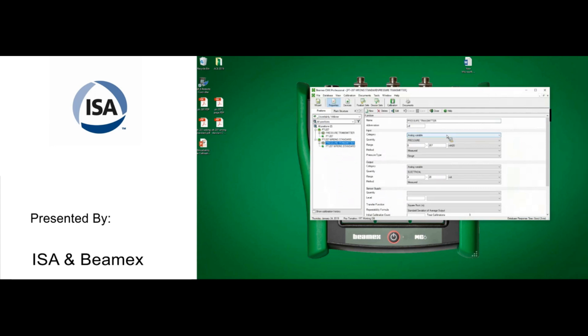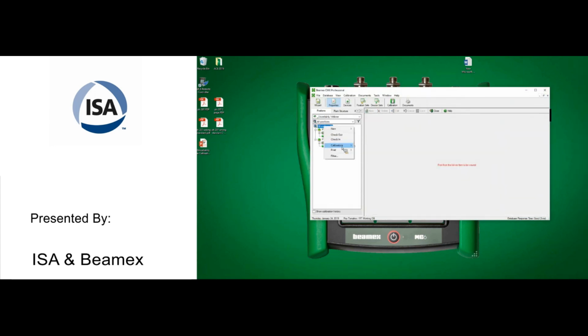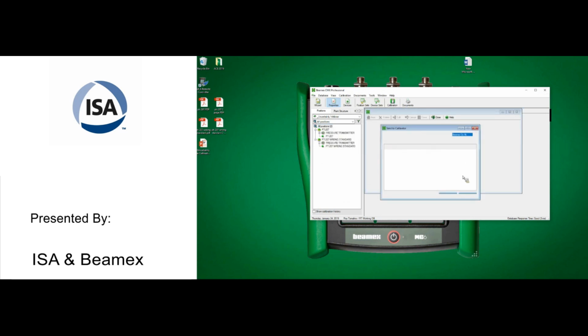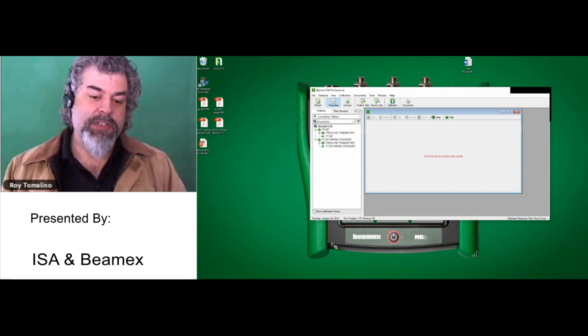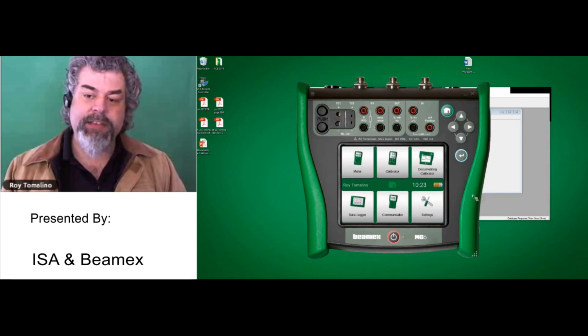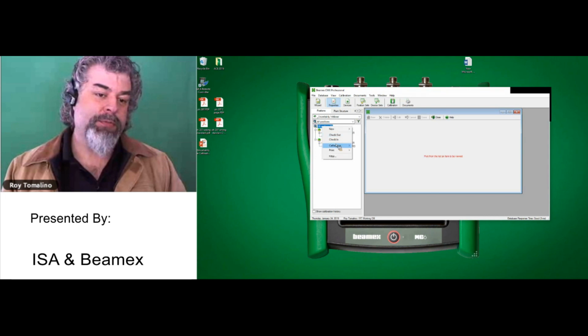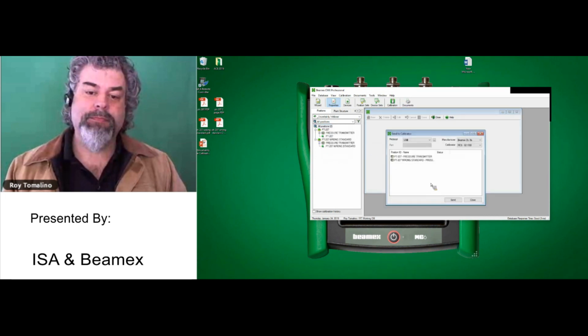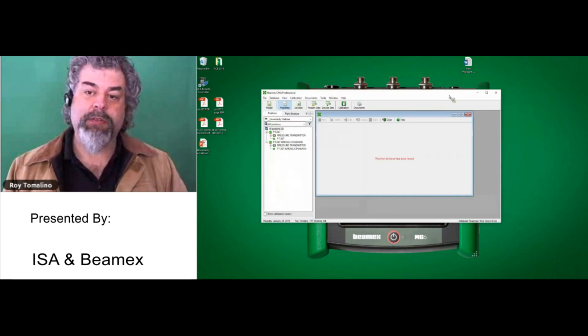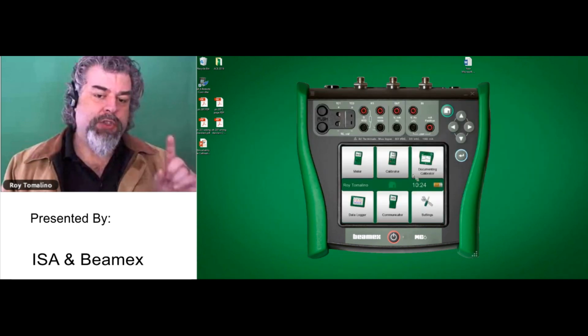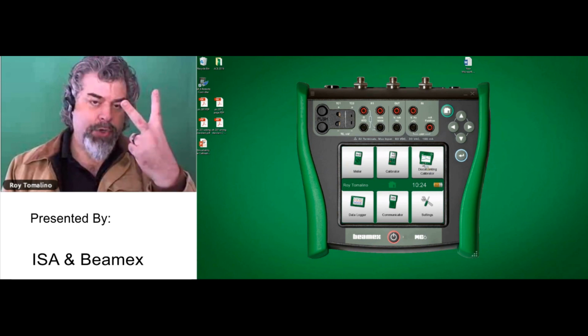What I want to do is, I am a good example of a bad example. First, I need to load up a couple of tests. I'm going to do a calibration. Let me send over these two tests. At this stage, let me disconnect this, and now I'll load up my calibrator. Sending them over. Okay, now it's sent over. Let me minimize this and fire up my calibrator. So we'll be doing a live calibration, actually two of them.